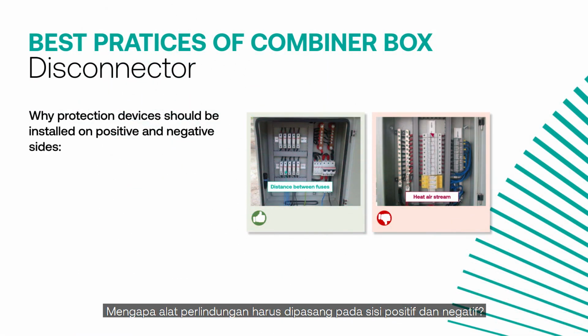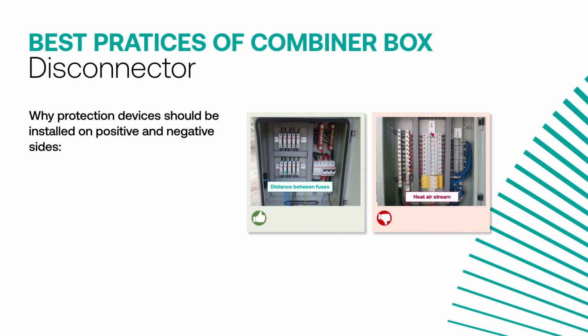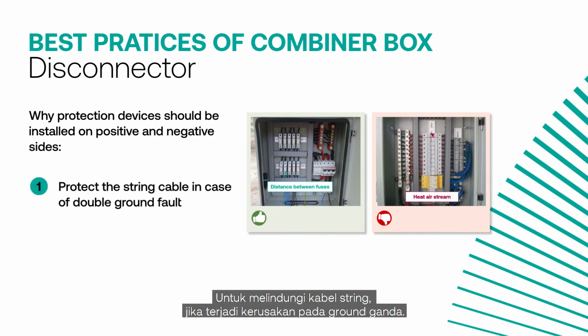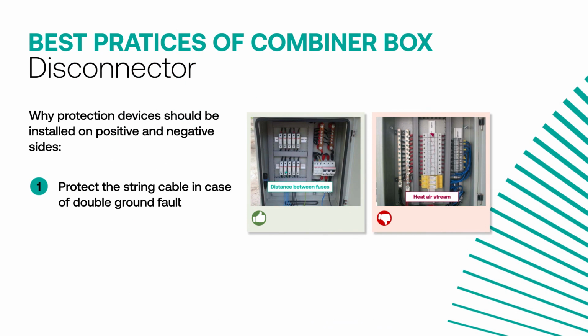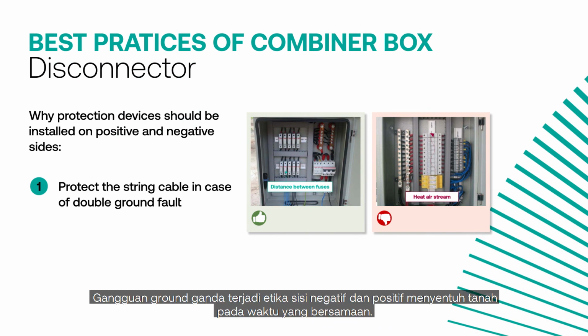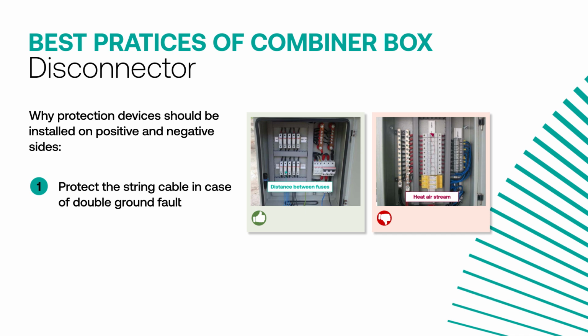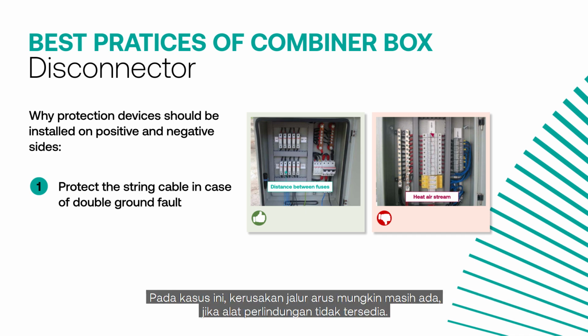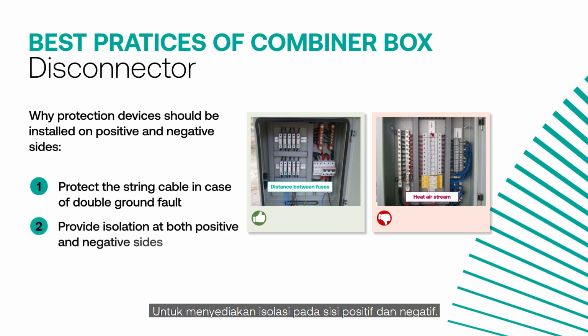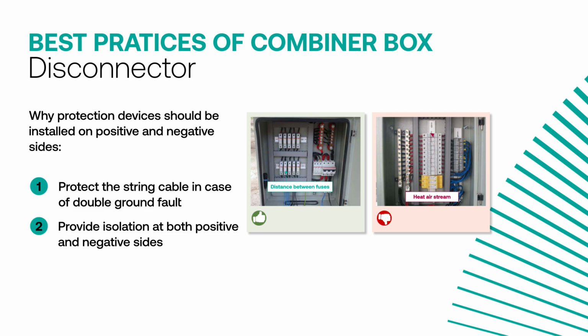Why should protection devices be installed on the positive and negative sides? To protect the string cable in case of a double ground fault. A double ground fault occurs when the negative and positive sides touch the ground at the same time. In this case, a fault current path may still exist if a protection device is not provided. To provide isolation at both positive and negative sides.